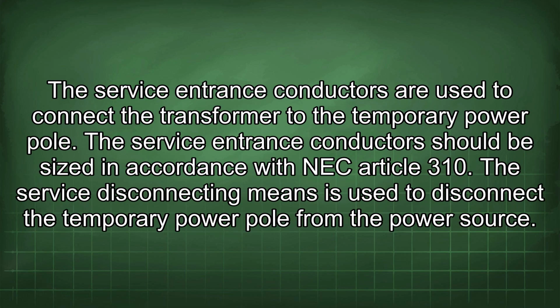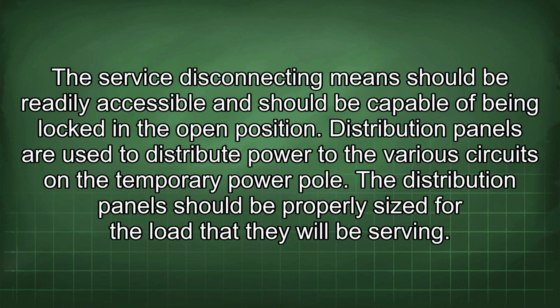The service entrance conductors are used to connect the transformer to the temporary power pole. The service entrance conductors should be sized in accordance with NEC Article 310. The service disconnecting means is used to disconnect the temporary power pole from the power source. The service disconnecting means should be readily accessible and should be capable of being locked in the open position.